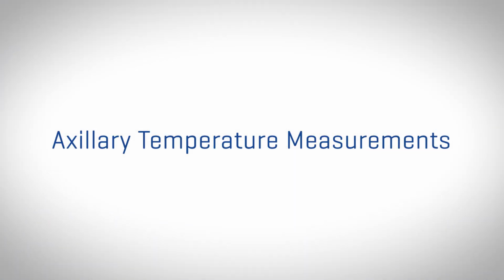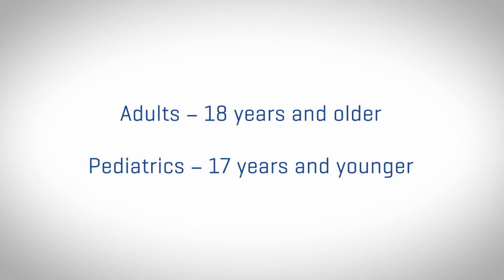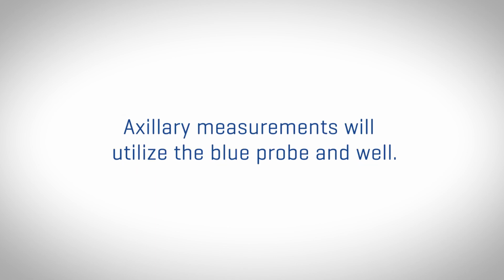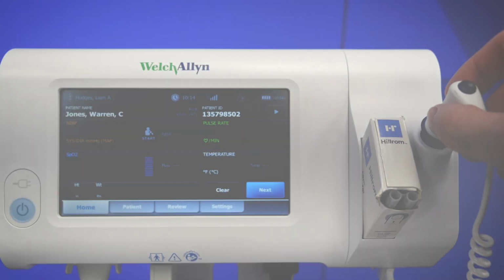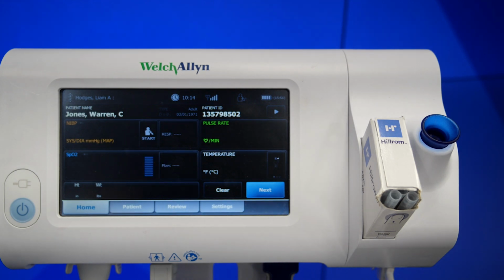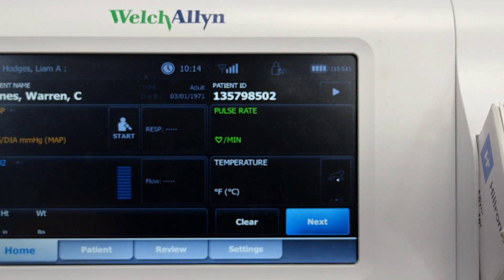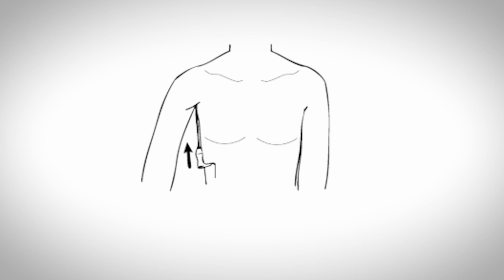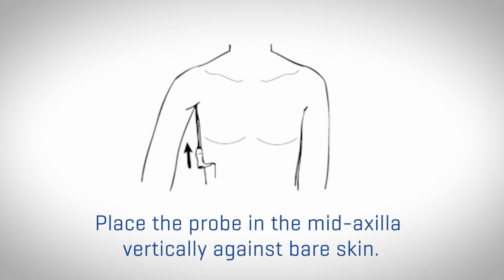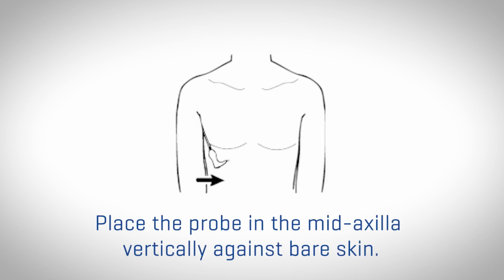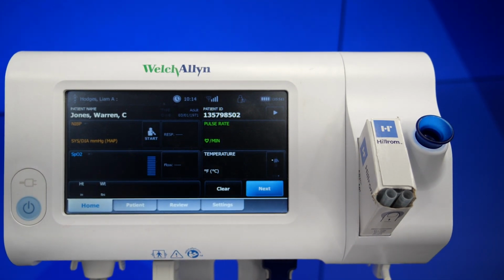Next are axillary measurements. In both predictive and direct modes, adults are considered 18 years and older, and pediatrics are 17 years and younger. To begin a predictive measurement, be sure the blue probe and well are inserted into the device. Follow the same procedure to select the correct temperature site by toggling between the locations, and then attach a probe cover. Next, lift the patient's arm, place the probe in the mid-axilla vertically against bare skin, and lower the arm so you have complete tissue contact. At the end of an axillary measurement, there will again be 3 short tones and the temperature reading will display on the device.